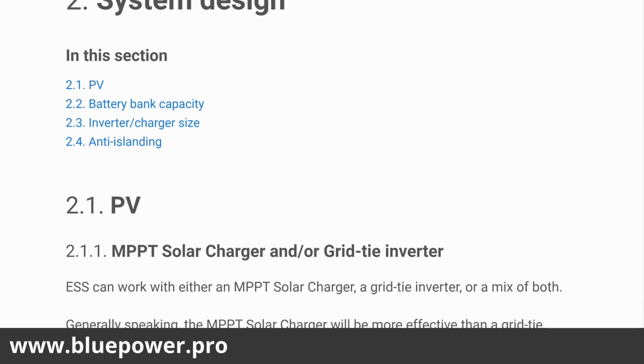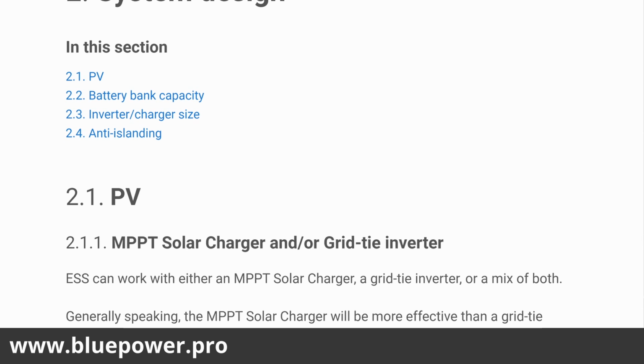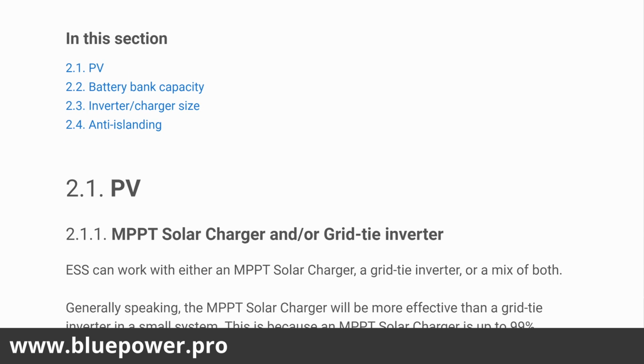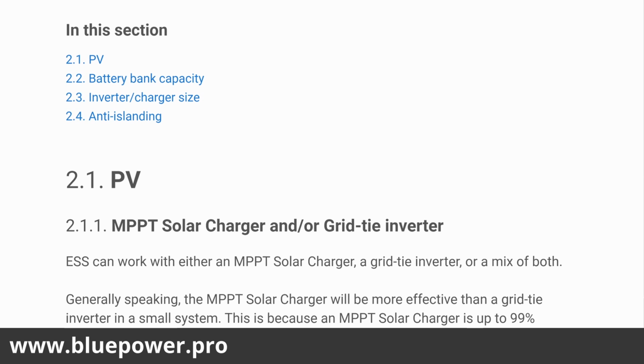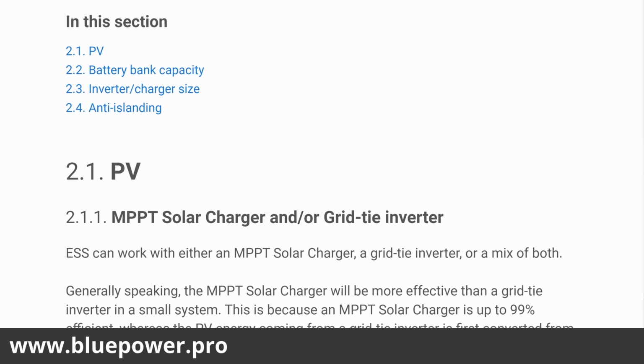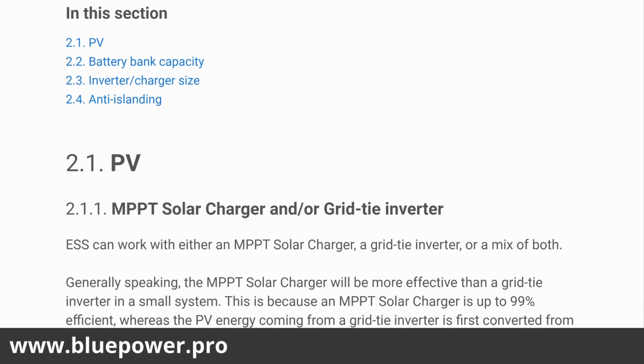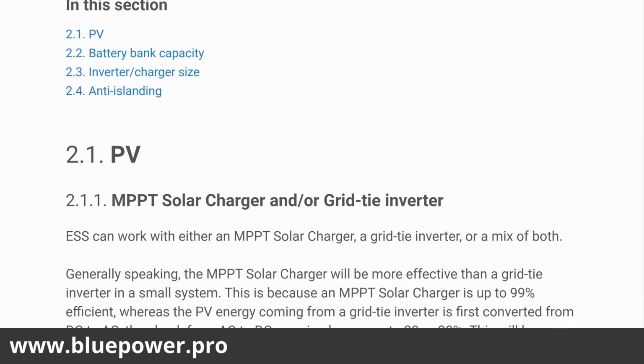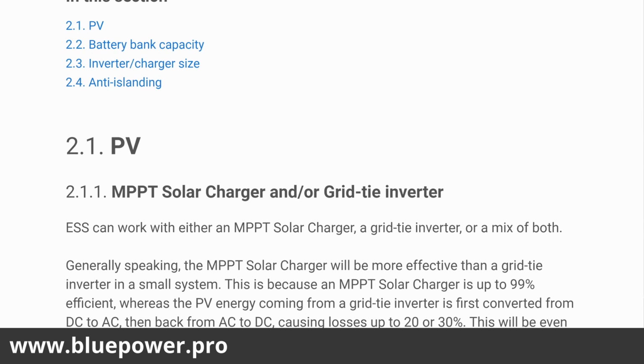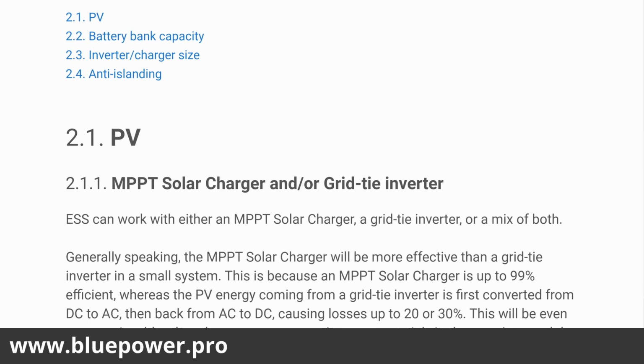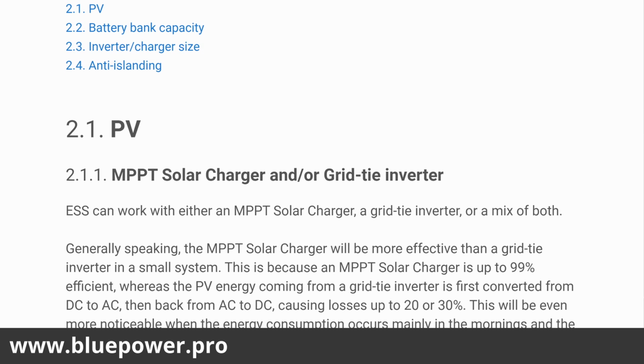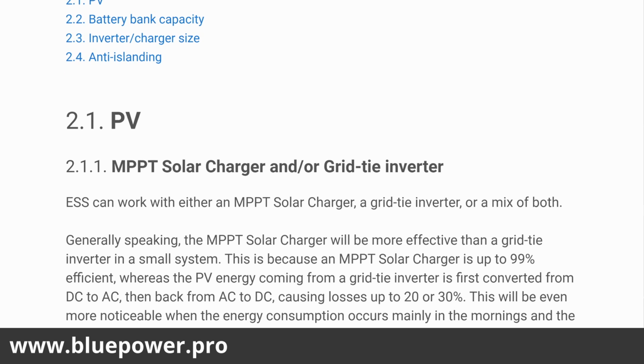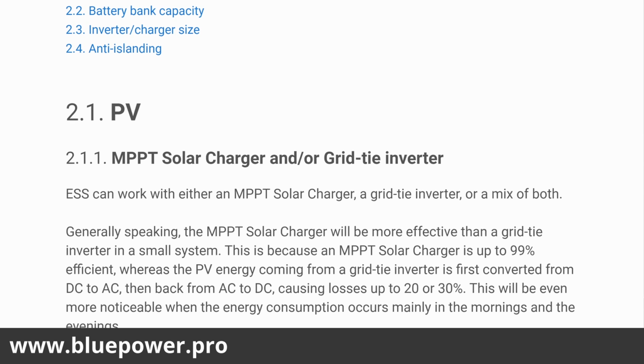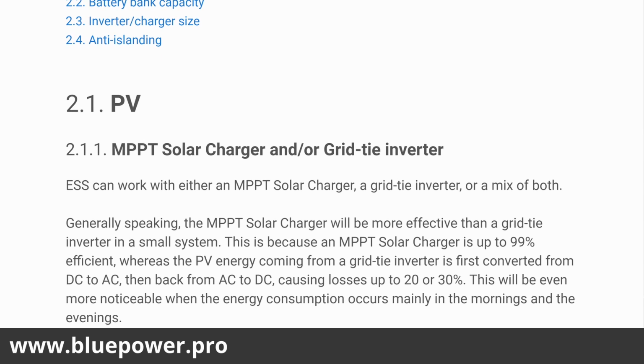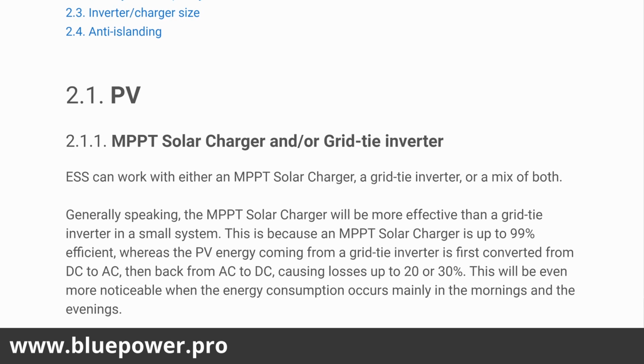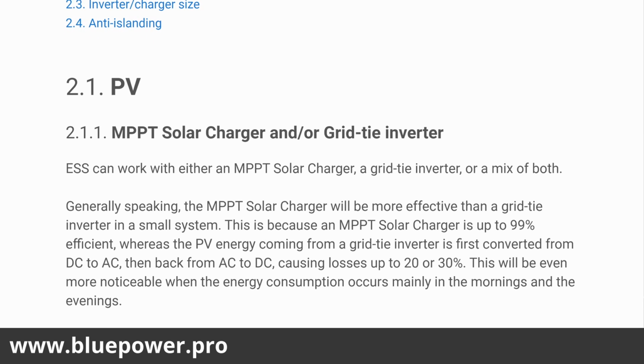So here we've got MPPT Solar Charge Controller and our PV grid-tied inverter. So ESS can work with either of those or with a mixture of both. So here I explain that generally speaking, the MPPT charge controller will be more efficient for charging or in a small system. This is because an MPPT Solar Charger is up to 99% efficient, whereas the PV energy coming from a grid-tied inverter is first converted from DC to AC, then back from AC to DC, causing losses of up to 20 to 30%. That's if you're charging your battery bank.